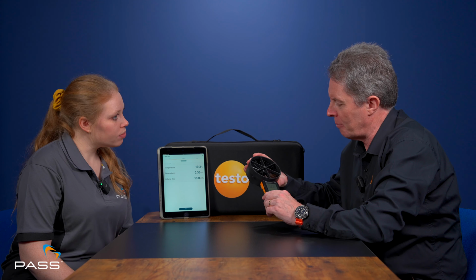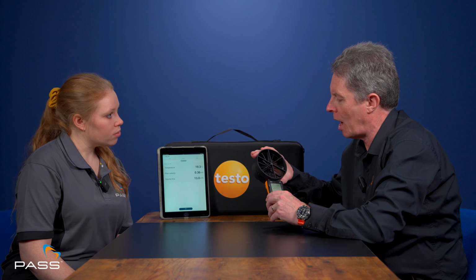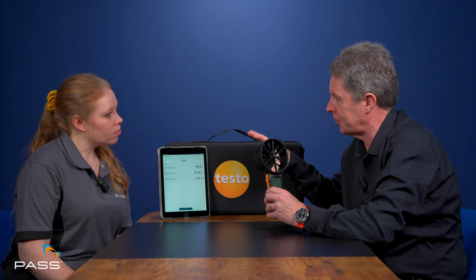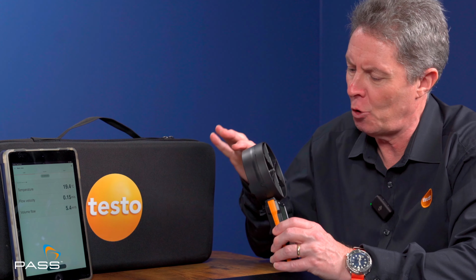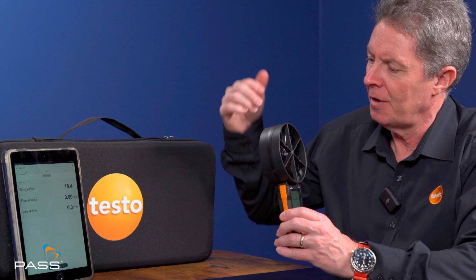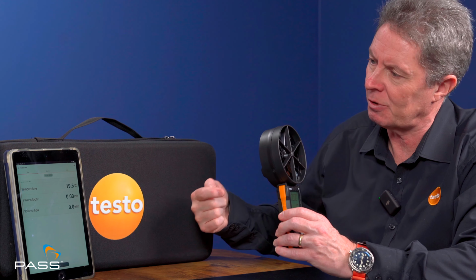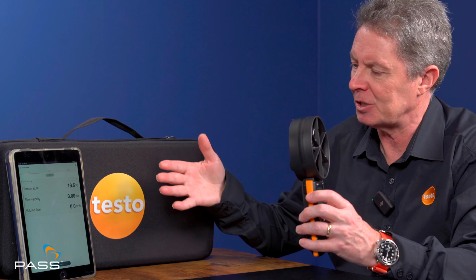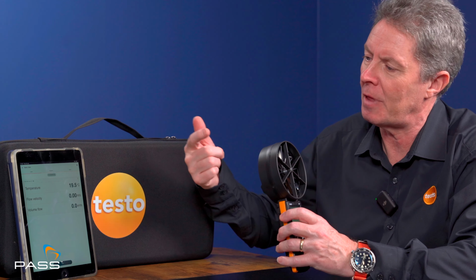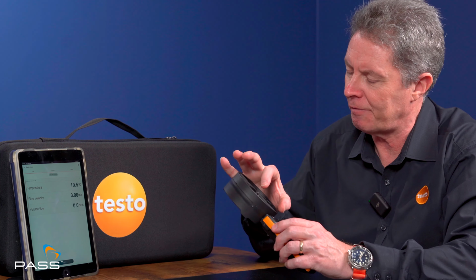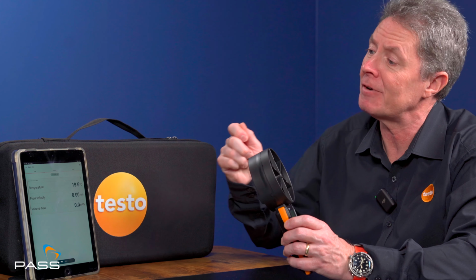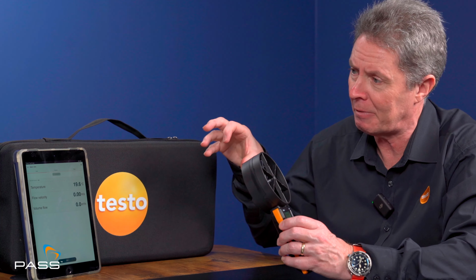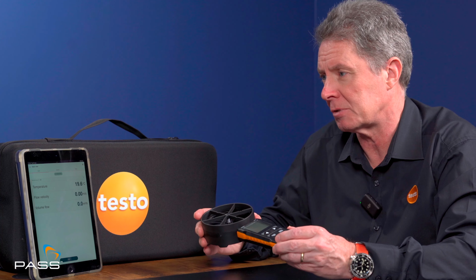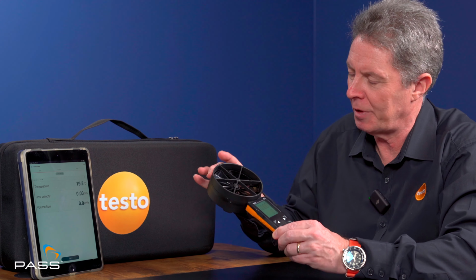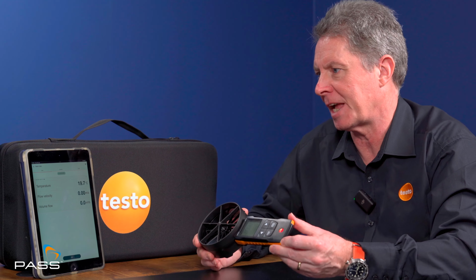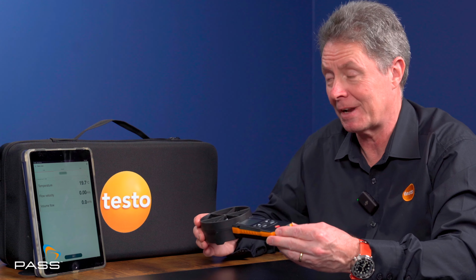Most 100mm vanes come with some form of capture hood as part of the kit - a hood assembly that matches the size of the grill you're testing, capturing all the airflow through that vent. With a smaller vane you'd have to do a timed average across a grill or outlet, giving much more inaccurate results. So a 100mm vane with a capture hood is really the benchmark standard for a proper ventilation engineer.